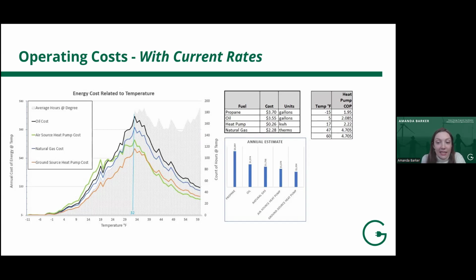And you will see that as the temperature decreases, it becomes less efficient. So at negative 15 degrees, it jumps down to 1.95 COP, which is actually still a really great COP. If you think about a natural gas furnace, the highest efficiency that you're going to get is about 98%. So in that metric, it would be 0.98. So the heat pump is still twice as efficient in terms of its optimization of fuel, even at this very cold temperature. And that is why this is classified as a cold climate heat pump.